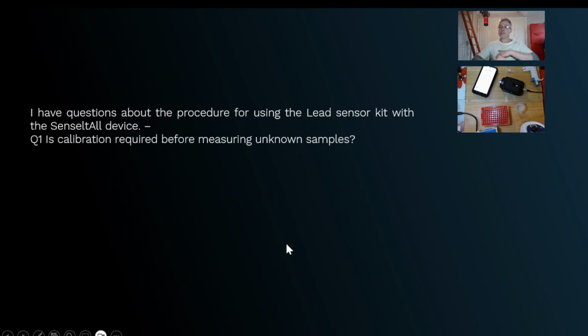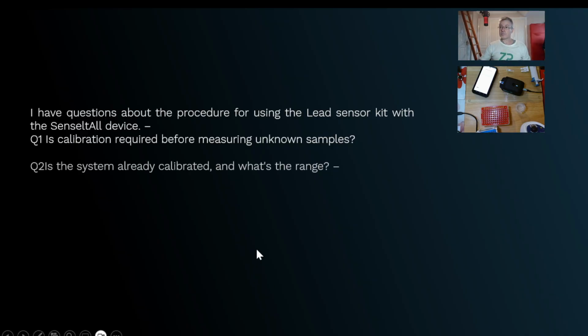So the question, is calibration required before measuring an unknown sample? The answer is no, calibration is not required before measuring an unknown sample. Now the only reason we get away with what's called global calibrations is because we make a very reproducible electrode. If we weren't doing that, then there would be a problem. So the quick answer is no.